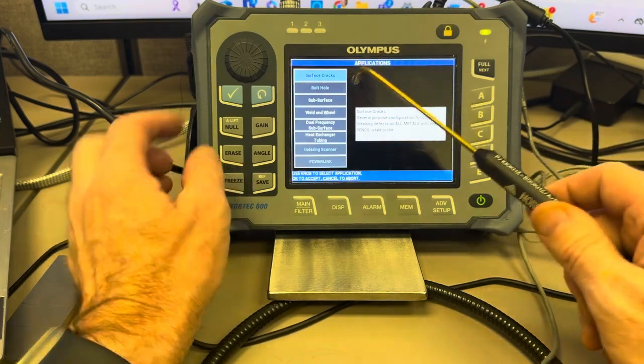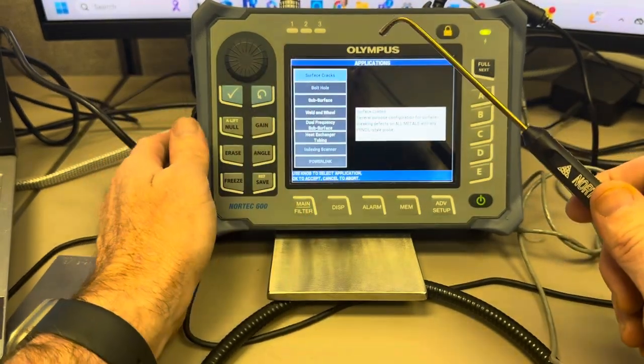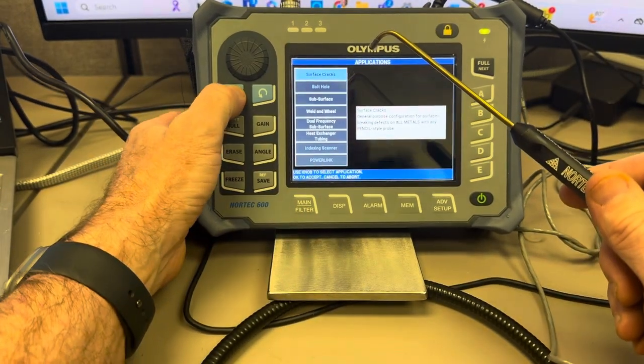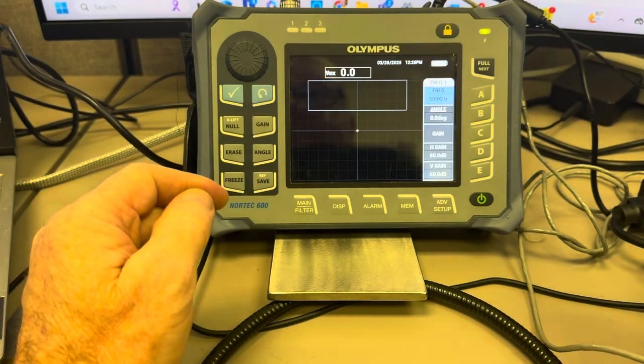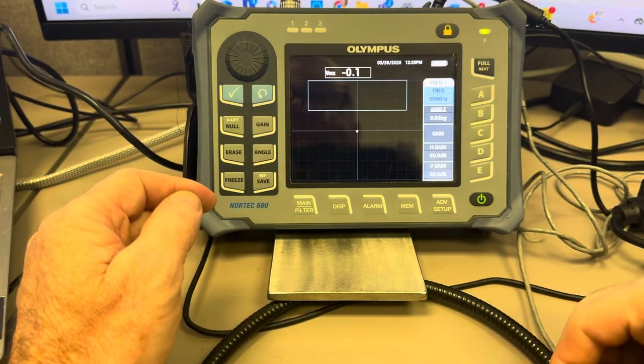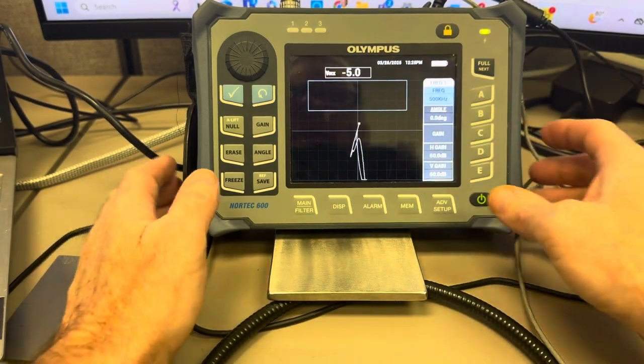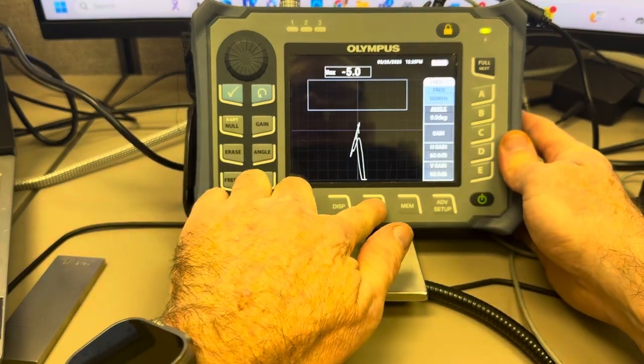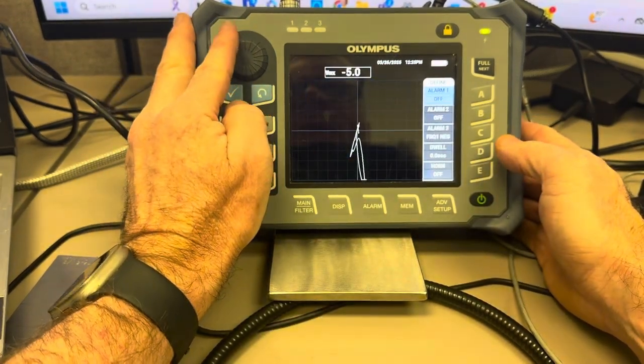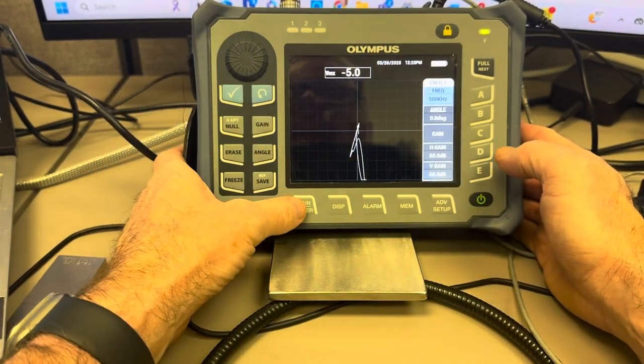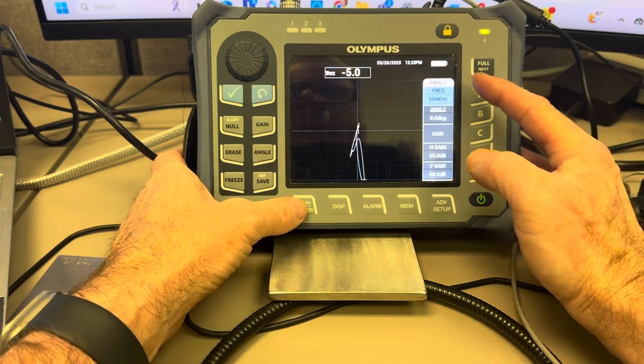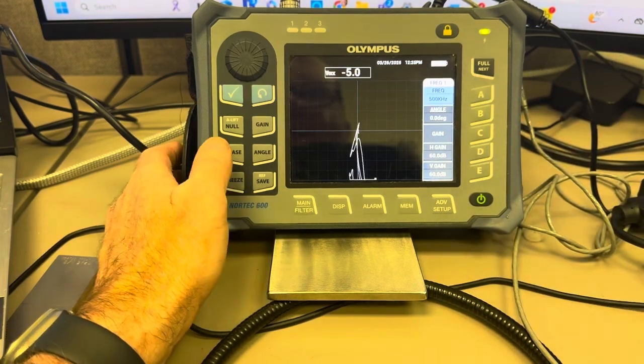So now that we've selected surface crack application with our smart knob, we'll just hit the arrow button to get into that mode. I don't want that box there, and I know that's an alarm box. So I'm just going to hit this alarm key. I'm going to turn it off with the smart knob, and then I'm going to go back to main. Now it's preset to 500 kilohertz. We'll just leave it there for now.